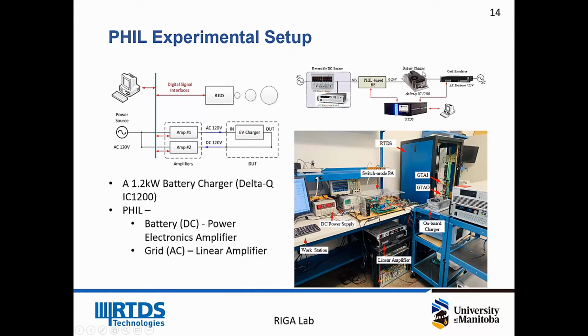On this page, you can see now we are using a physical battery charger. That is from Delta-Q, and it is a 1.2 kilowatt battery on-board charger. This one is a block diagram. We need to use two amplifiers. One is for the AC source, another one is for the DC, that means the battery. And here you will see that for the grid side, the emulator will use the linear amplifier connecting to the battery charger, and for the battery side, the DC side, we use a power electronics emulator, and then both of them connect to RTDS. And you can see the laboratory setup here: the charger, RTDS, A to D, D to A cards, linear amplifier here, power electronics amplifier, and also the RSCAD to provide models to RTDS.